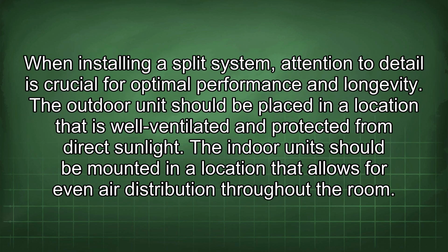When installing a split system, attention to detail is crucial for optimal performance and longevity. The outdoor unit should be placed in a location that is well ventilated and protected from direct sunlight. The indoor unit should be mounted in a location that allows for even air distribution throughout the room.